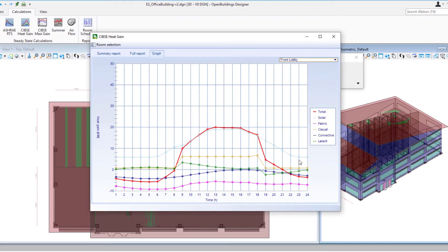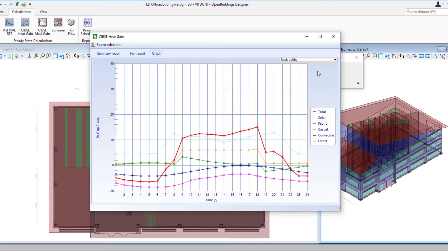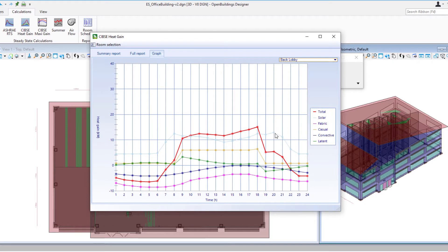I will notice here on the front lobby it's almost up to 20 there. If I switch and compare that to the back lobby we'll see that again the solar load is the greatest although it's not quite as high on the graph. And of course that's because our front lobby is south facing and our back lobby is north facing. And so we could take a look at that and see if we could make a change.